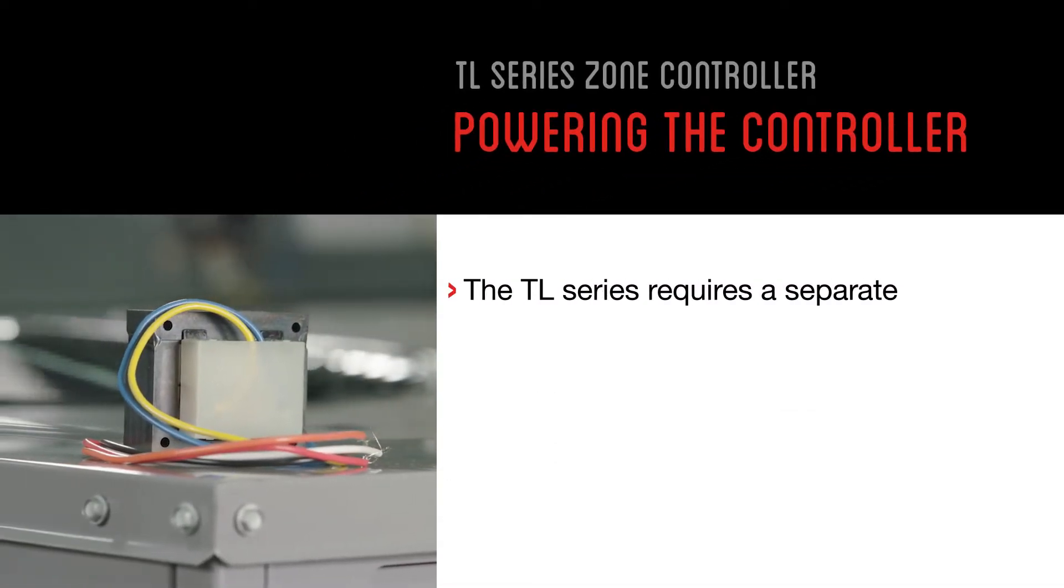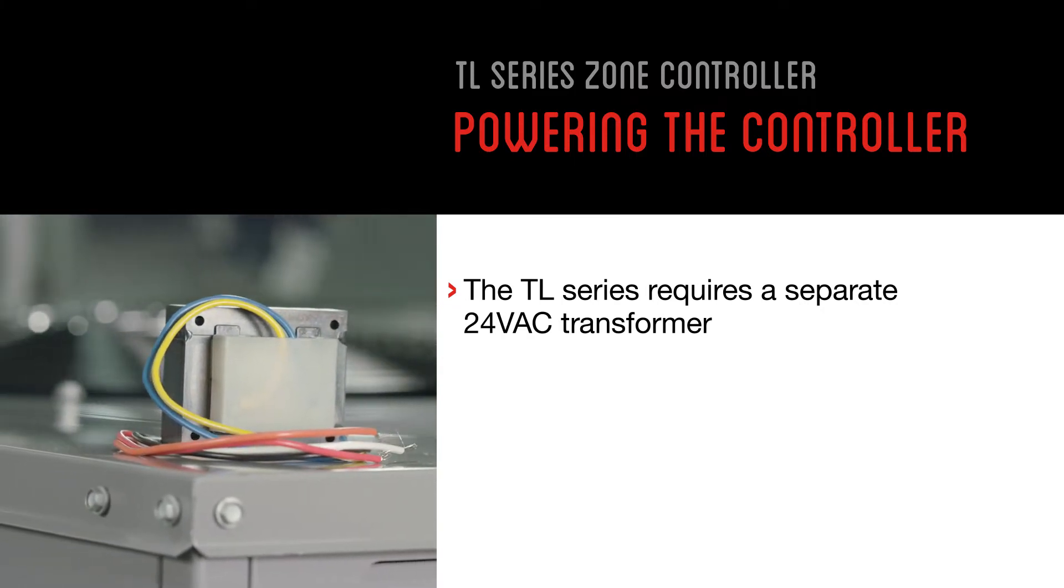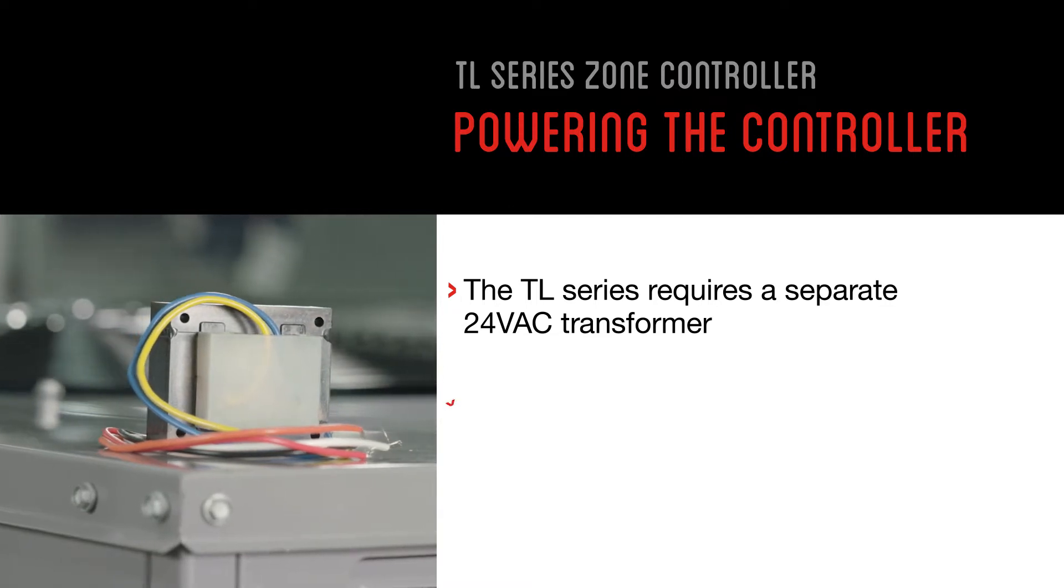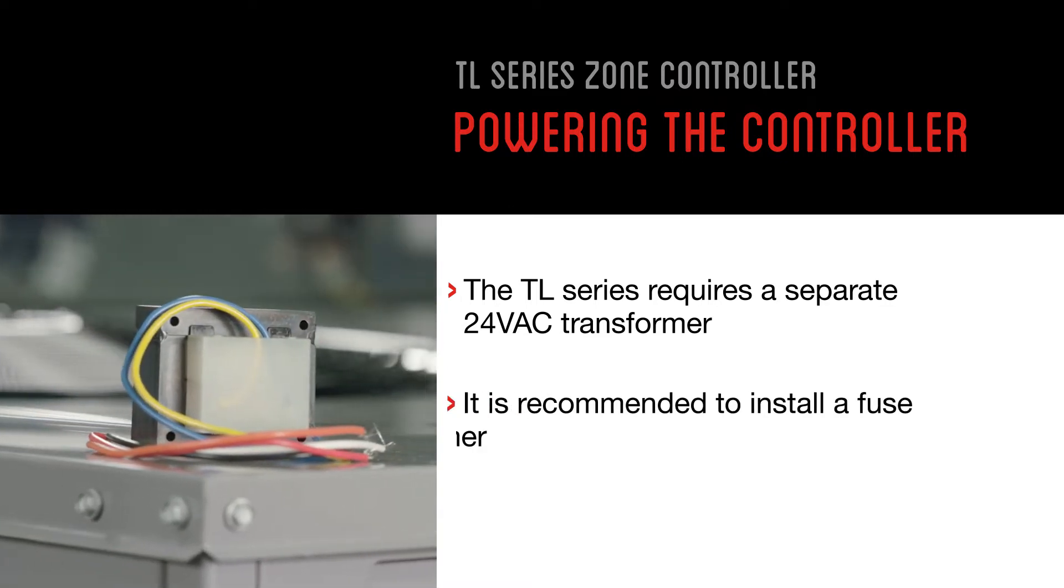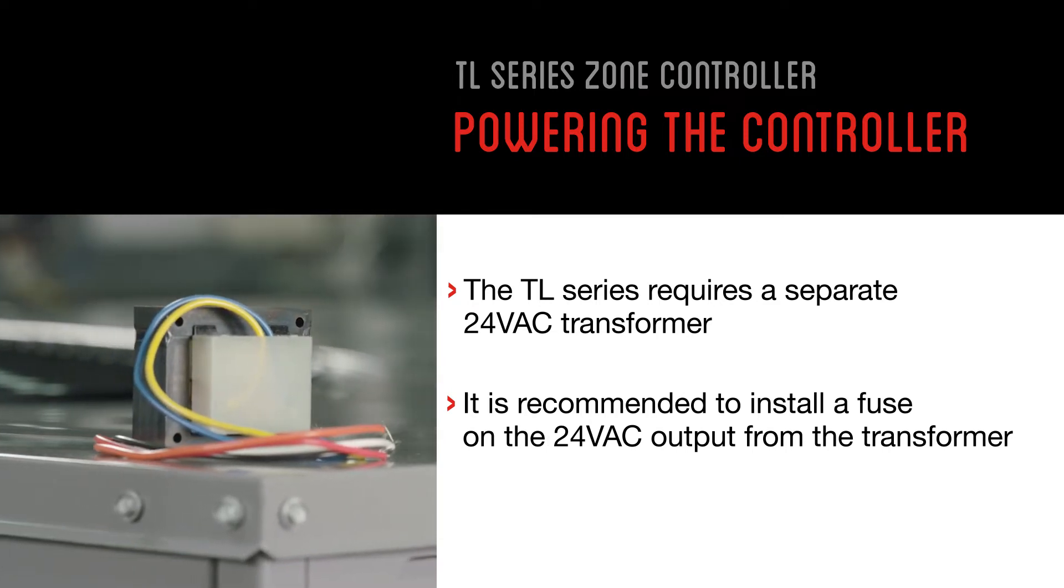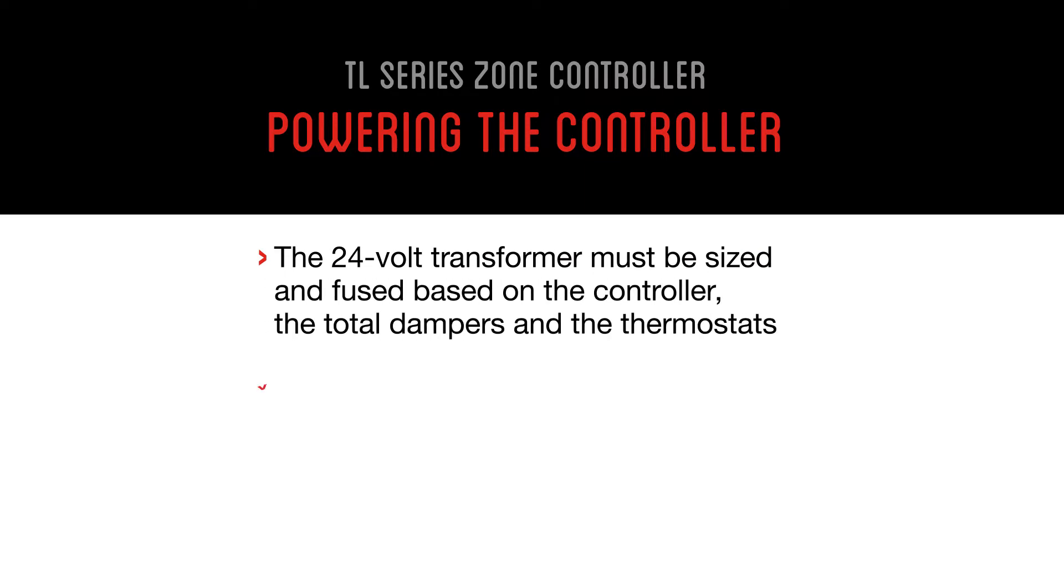Be aware that the TL series system requires a separate 24-volt AC transformer, which is not included, for powering the TL series controller, zone thermostats, and dampers. It is recommended to install a fuse on the 24-volt AC output from the transformer. Note that the 24-volt transformer must be sized and fused based on the controller, the total dampers, and the thermostats. Reference the transformer sizing charts in the install guide.